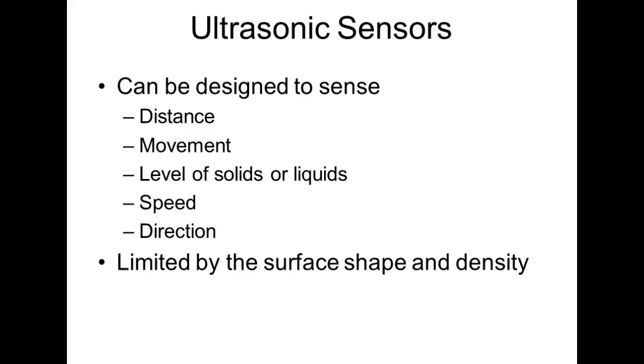So ultrasonic sensors can be designed to detect distance, movement, or level. Y'all understand the difference between distance and level? Level is a vertical measurement. So when you're down there and you see the big tank farm with all that gasoline in it, what do you think they use to detect the level? They use ultrasonic sensors - they're actually in the top of the tank, and that's the way they measure the level of the fluid inside.